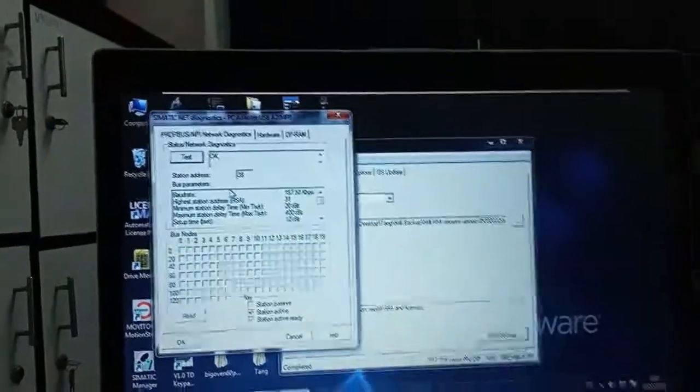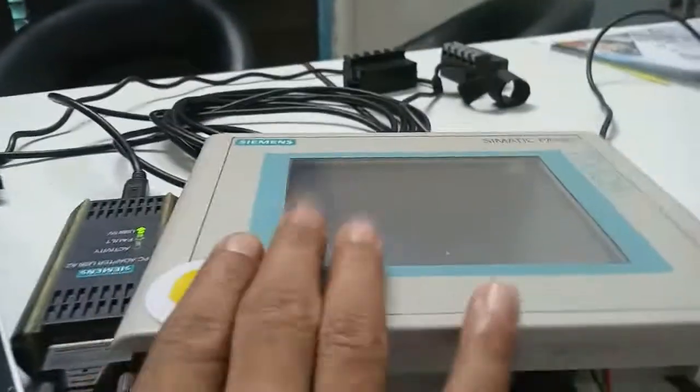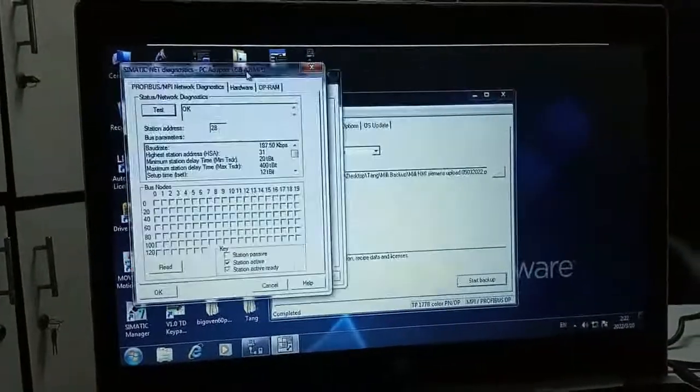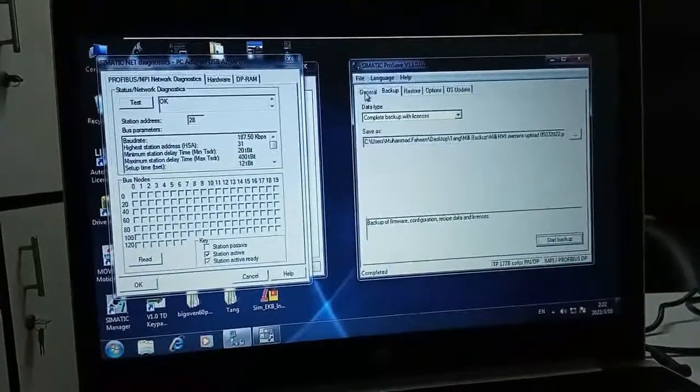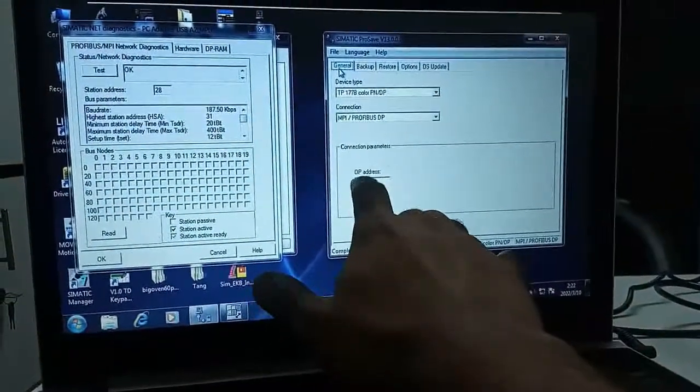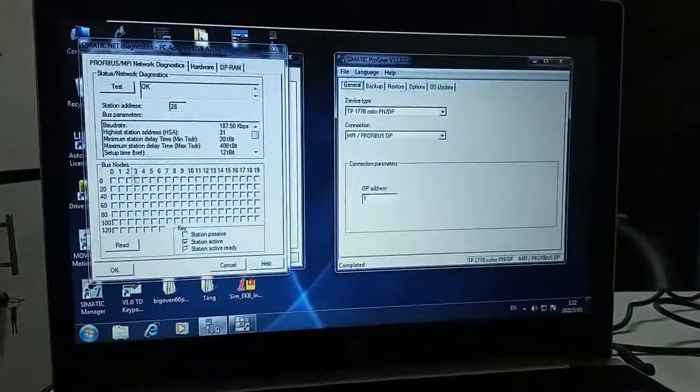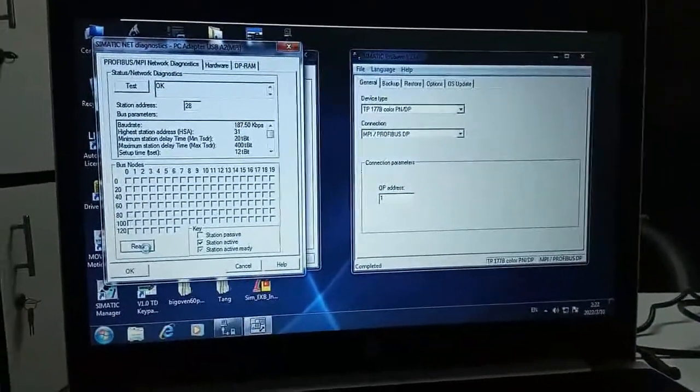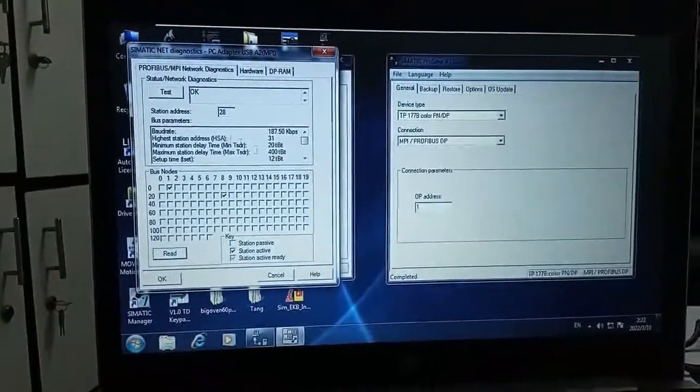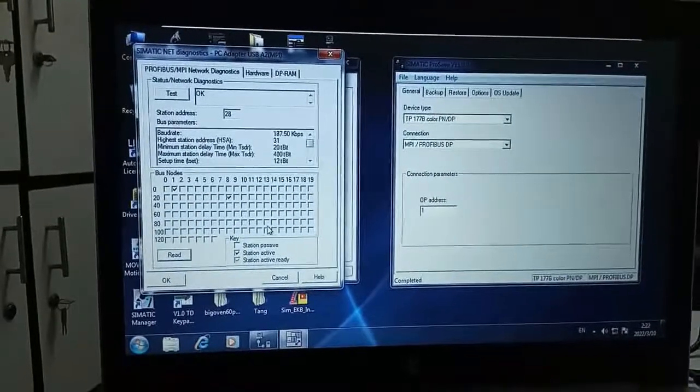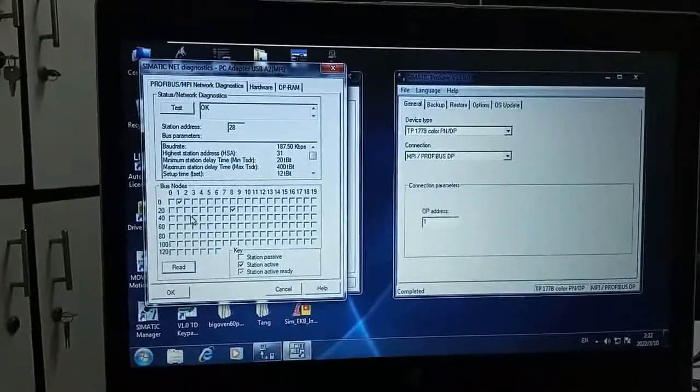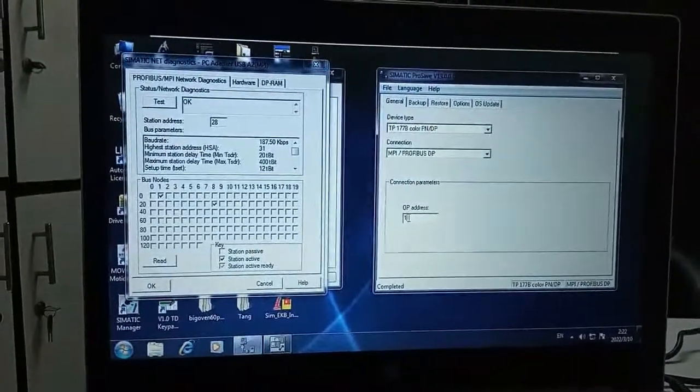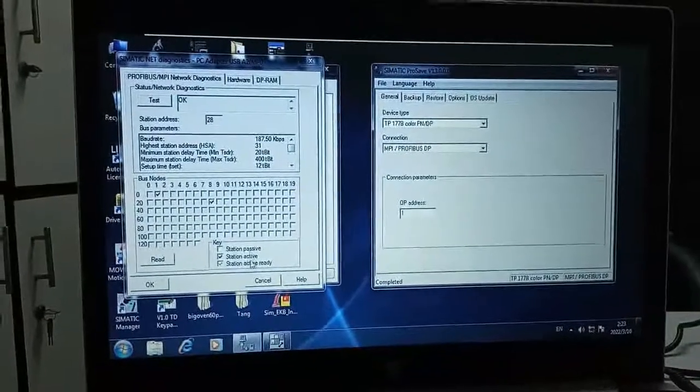If you want to see the HMI address, which was OP address as you can see here, here you need to set the OP address. OP means operating panel address or HMI. Then you need to click on read button in the PGPC interface and it will show you the address of your OP. Here it is, this is one. That's why I have put one here to take a backup from the HMI.